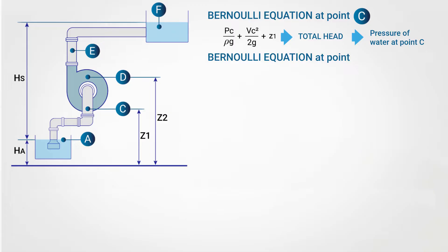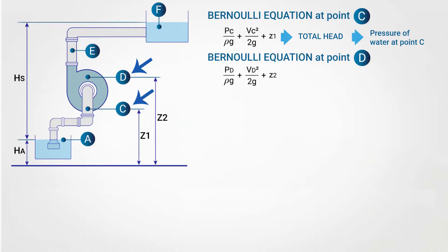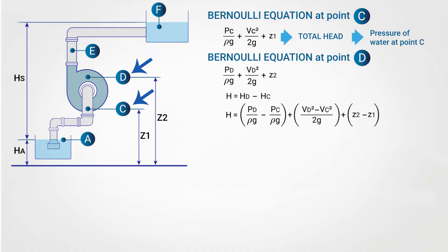A very similar application of the Bernoulli equation is made at point D, which is where the water is leaving the pump. The equation is: PD divided by ρg, plus VD squared divided by 2g, plus Z2. To calculate the total head of the pump, I subtract the total head at point C from the total head at point D, giving HD minus HC, which equals (PD − PC)/ρg plus (VD² − VC²)/2g plus (Z2 − Z1), yielding H.